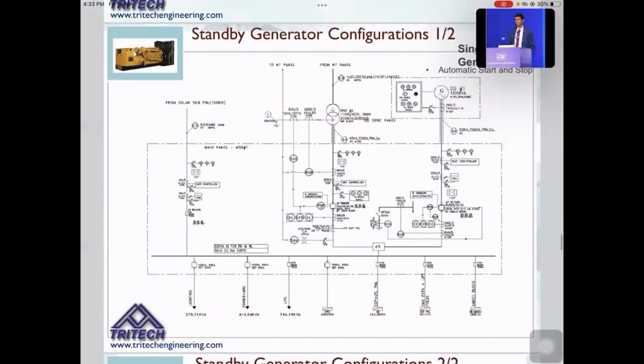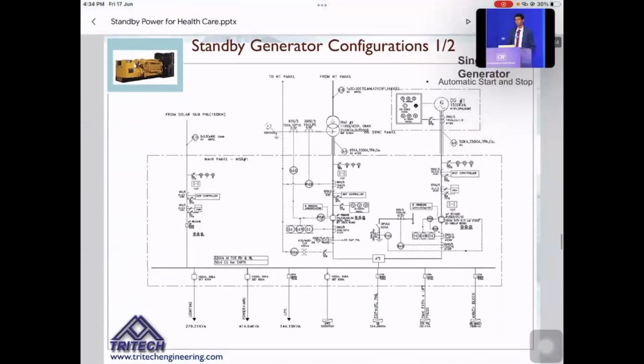So I've just highlighted one scheme. This is an electrical scheme which shows a transformer and a single generator with a transfer switch. So in this case, you just need start and stop functions only. You will be disconnecting the main supply and switching on the generator and connecting it to the main. So in the case of failure, for smaller systems, this configuration works well. You have only one generator, one transformer. Once the power fails, you switch on the generator. Then once the voltage and all the parameters are okay, you switch on the breaker, connecting the generator into the main bus. So this is how the connections work. So we have an automatic transfer switch and all that. This is the basic configuration.